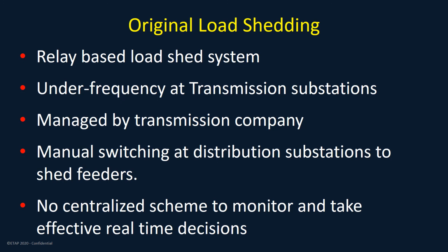Originally, the load shed system at NPCL had consisted of under-frequency relays at the transmission substations. From these relays, the signal propagated to the network to shed loads. The relays were managed by the transmission companies. They had a fixed priority and were hard to reconfigure. At the time, there were less than 20 substations. Currently, the utility is growing at a fast pace, and they need an intelligent solution that can be updated from a central location and can be optimized to maintain the quality of service.